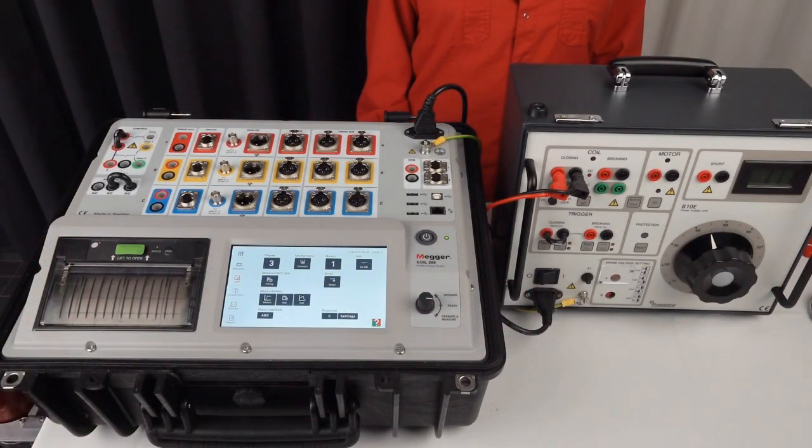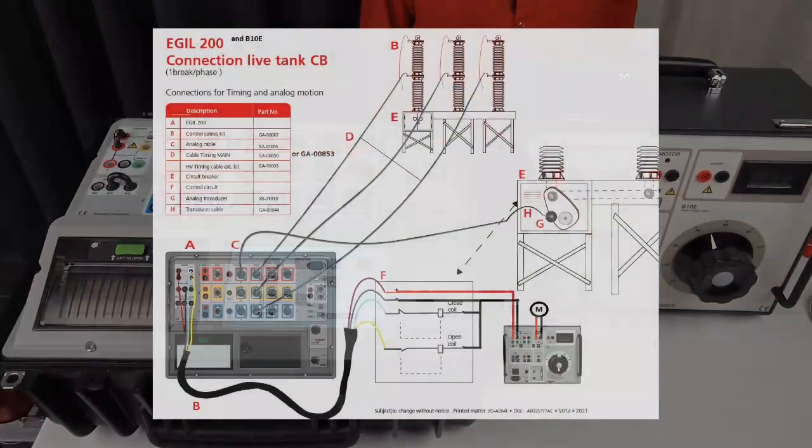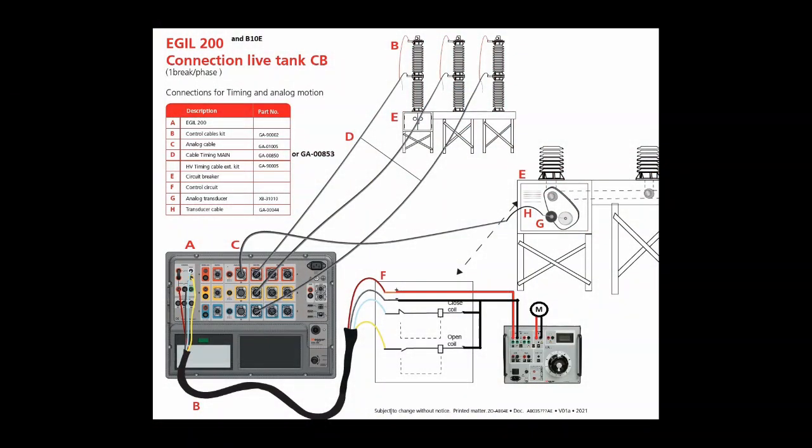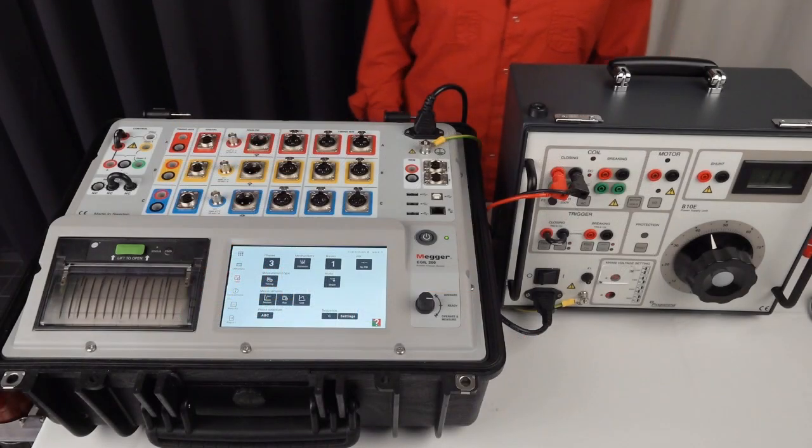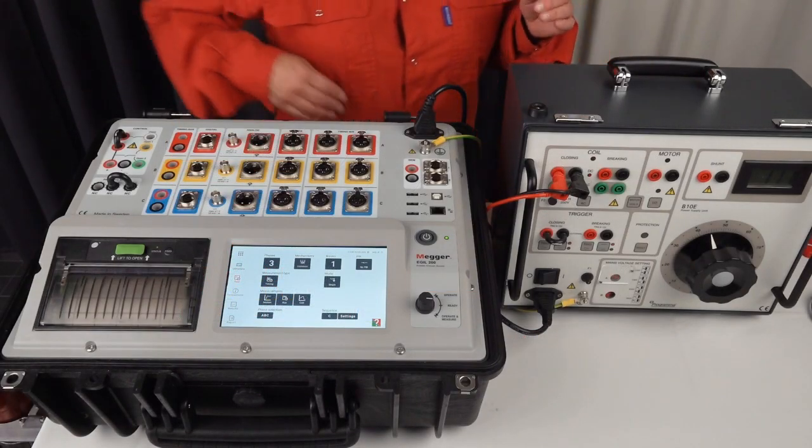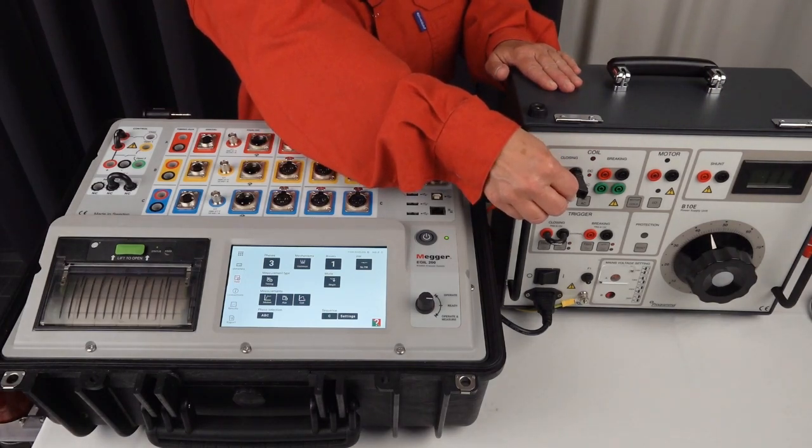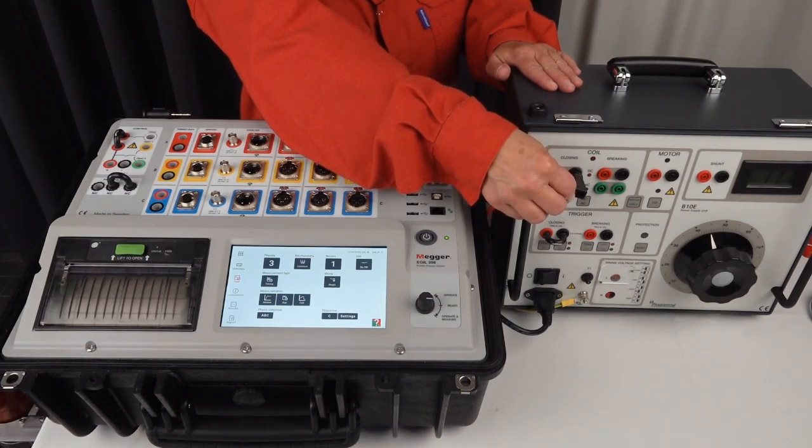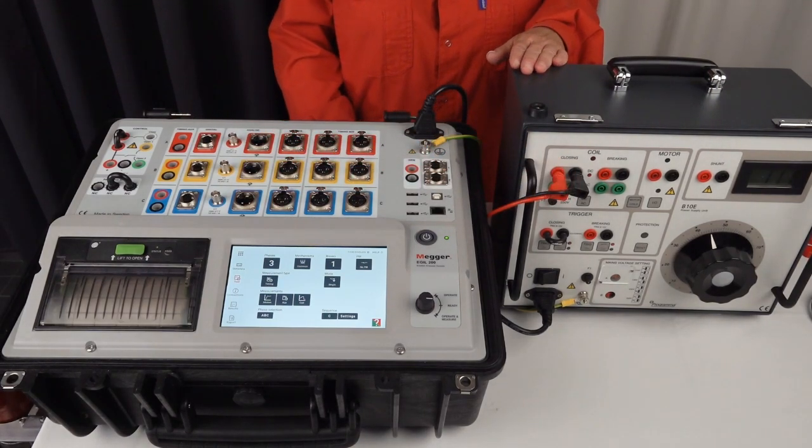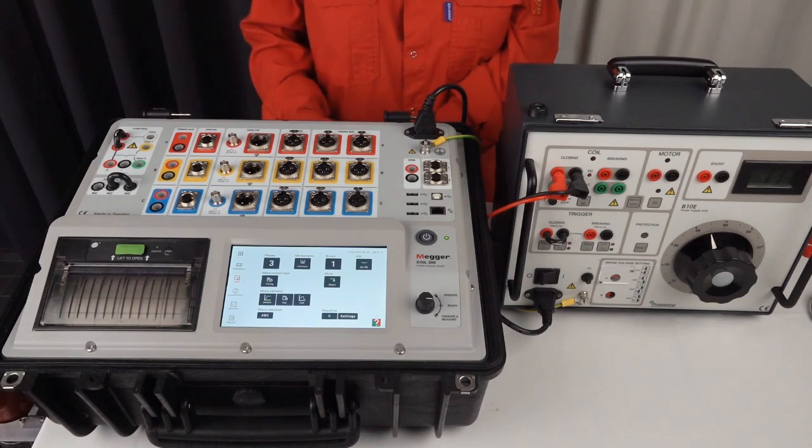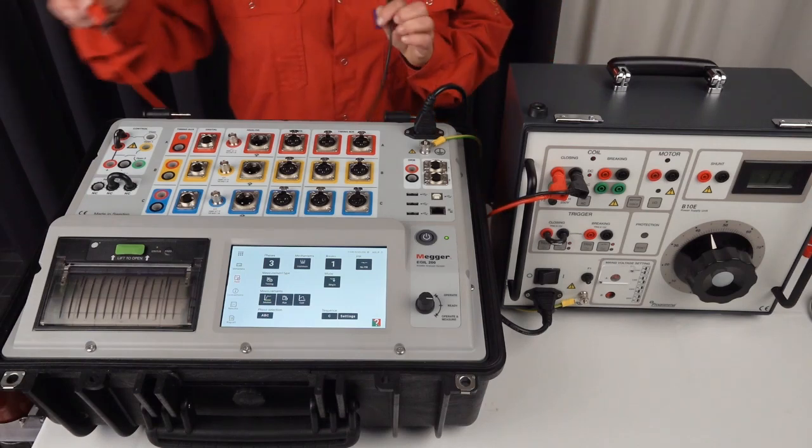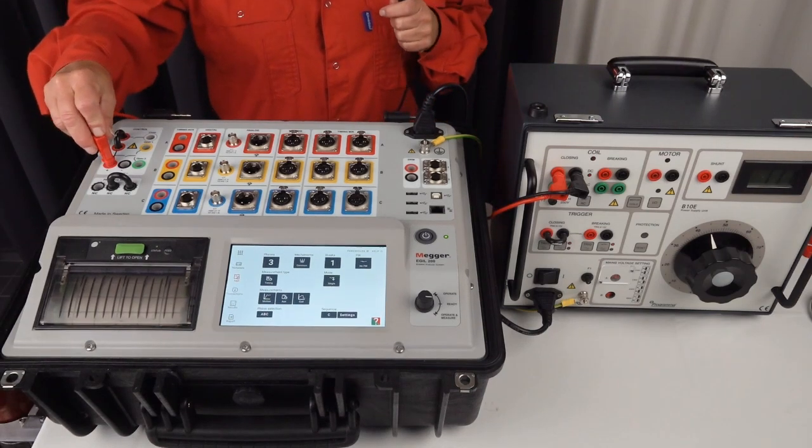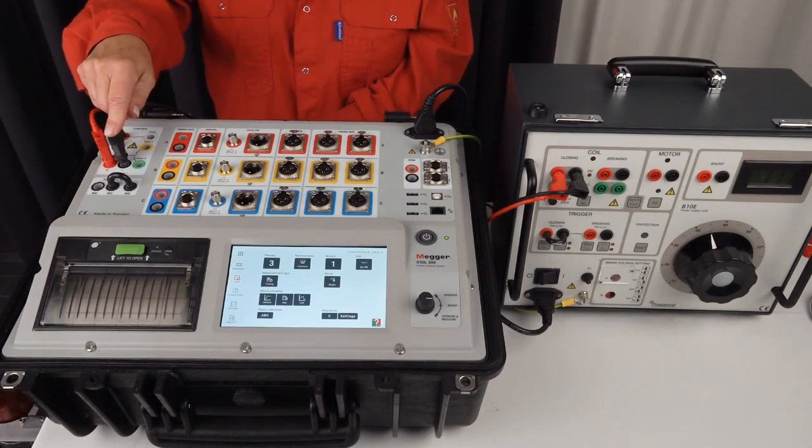I start with the connections. I have a connection diagram to follow which shows all the details. This document is in the delivery of EGIL 200 and I start following the instruction. I connect the plus and minus to supply to the circuit breaker analyzer and I connect the plus and the minus on the analyzer.